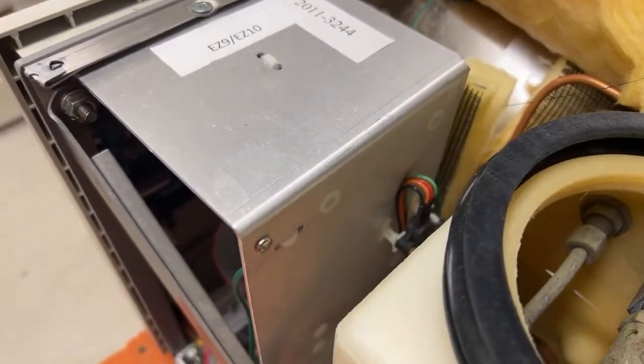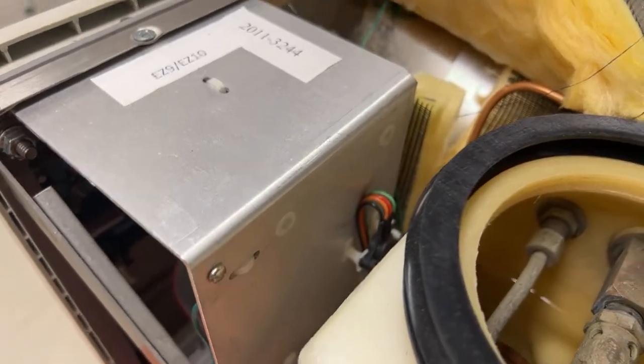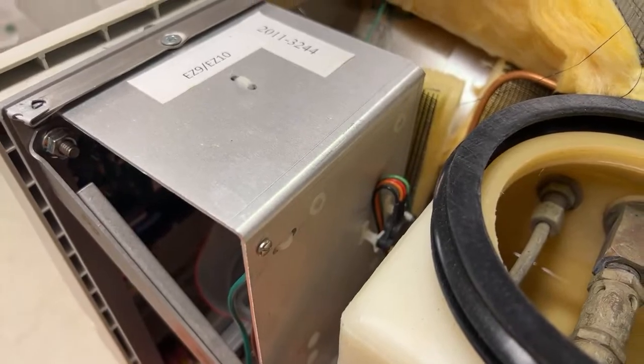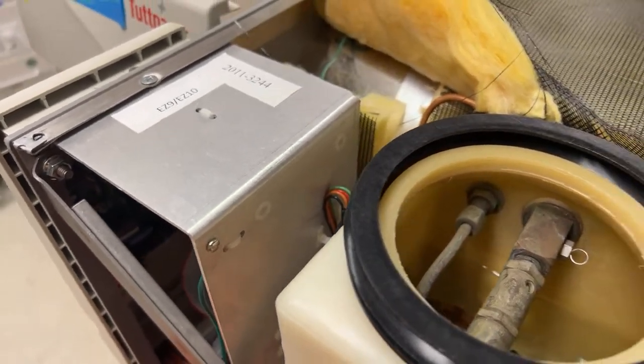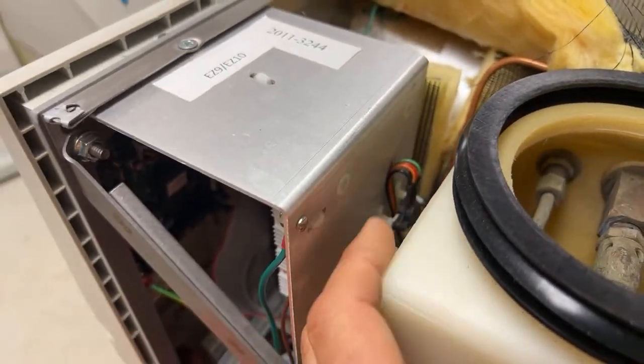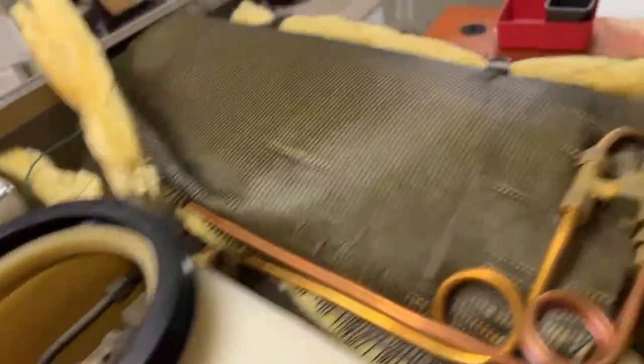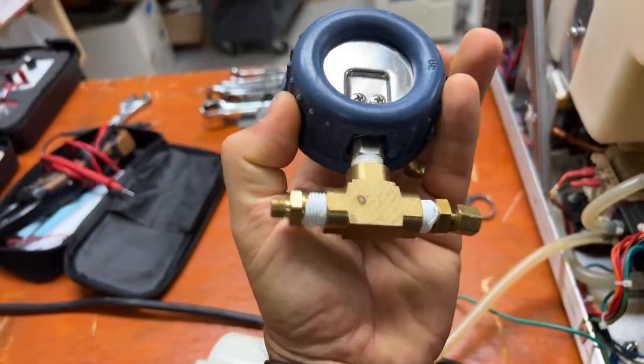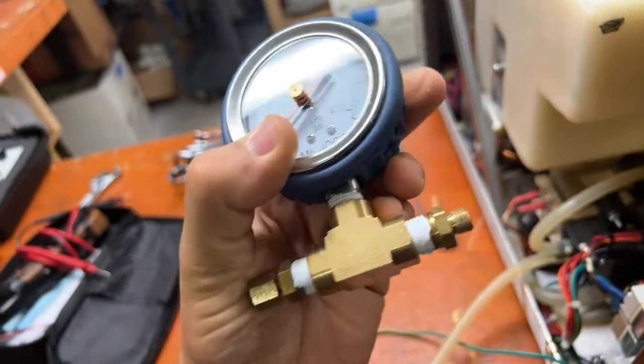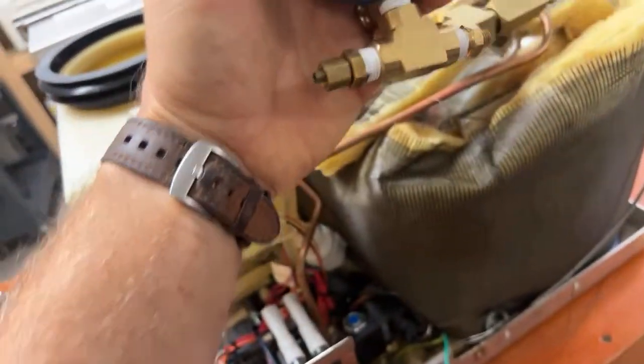The reason we're going to do that is because that little component right there is a pressure transducer. My understanding of a transducer is that it converts one reading into another, so this one converts pressure into an electrical signal. Because we don't have a physical gauge to reference, we're going to put our pressure gauge right here. On the RPI kit, it just has a female to male fitting that will go right in place. So I'm going to have Kyle go ahead and install that. Here you go. We'll come over here and take a peek from this perspective.